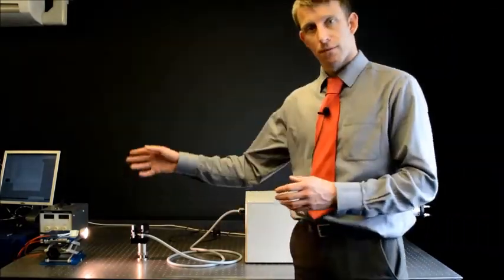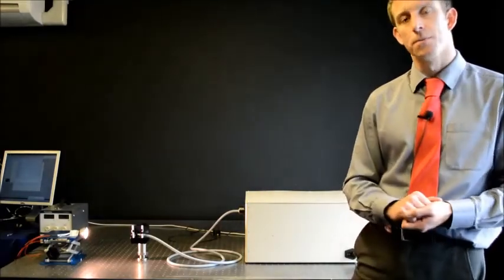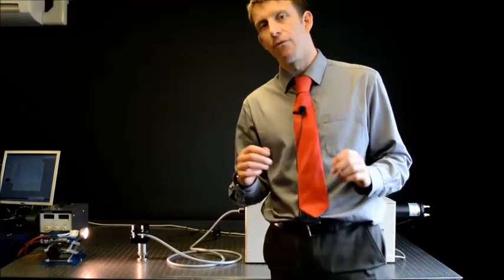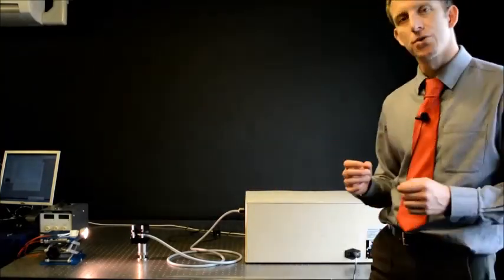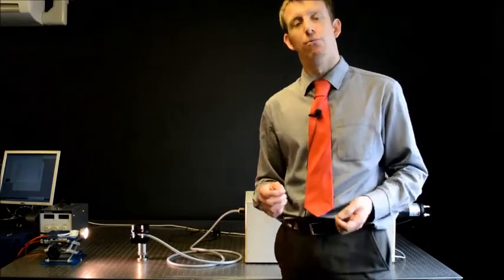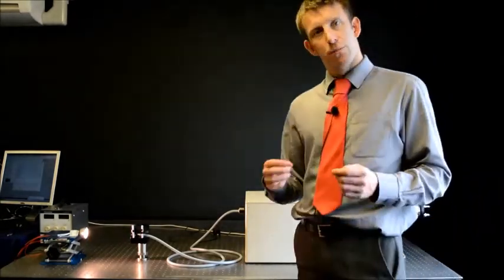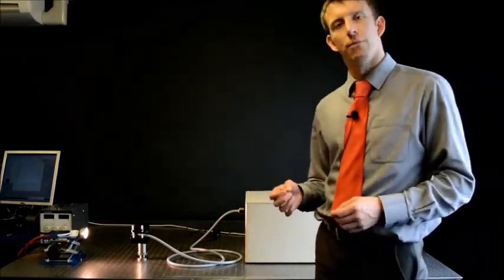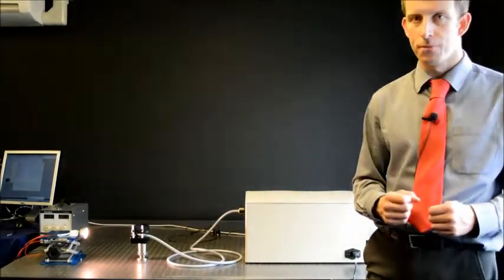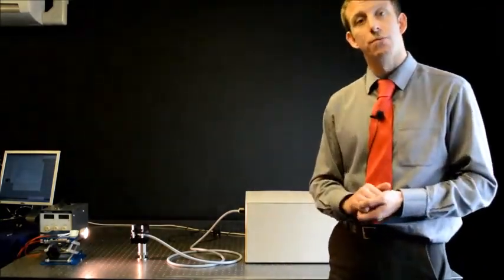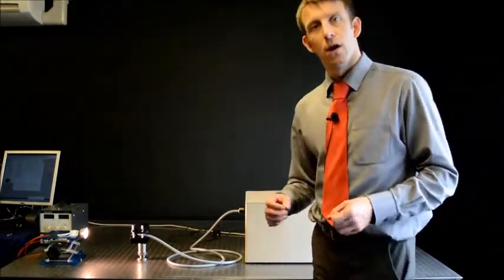One simply measures as we have organised here. Where the source is larger than 11 milliradians, then one must pay attention to the apertures required in the measurement of blue light radiance. This will be described in more detail in another presentation. Essentially, the blue light exempt risk group should be performed over a measurement field of view of 100 milliradians. And in performing the measurement at 200 millimeters distance, we should place an aperture of 20 millimeters diameter at the source. Clearly, where the source is smaller than 20 millimeters, then one need not place an aperture there.